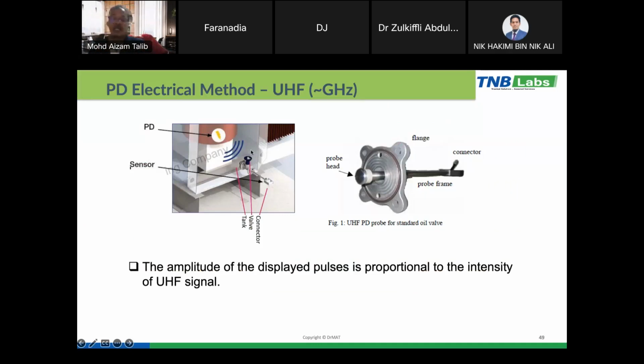Okay, the other sensor, electrical method, we can use the UHF sensor, where we put a sensor inside the transformer. So when there is a PD occurring in the transformer, it will generate an electromagnetic wave, and it will be picked up by the UHF sensor.